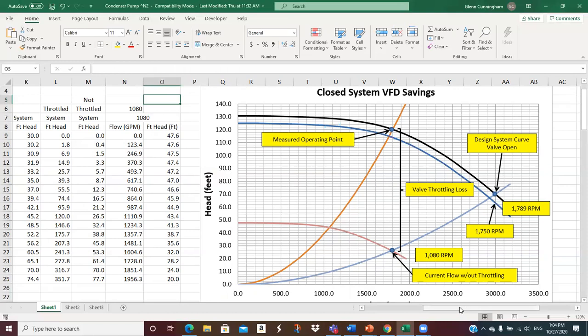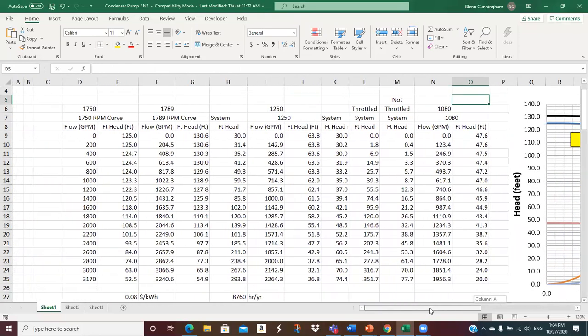Then I took my strobe out there in the field, and yeah, there's the 1750 curve. It's 1789 is what I measured. Well, that's a little faster. So let me take that into consideration. So that's the number I'm pulling. This is just a tag over the columns. And so see, in this curve, it's D9, and then I adjust it. I'm locking down F6, which is this, divided by D6, which is this. And so you see at this 200 GPM, when I translate that point, it translates into 204.5. And that's the speed ratio to the first power, okay?